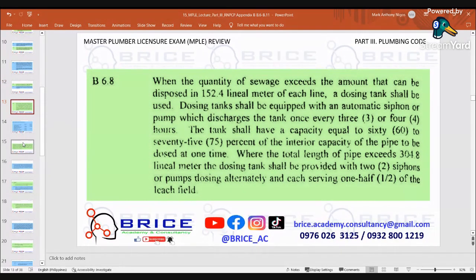When the quantity of sewage exceeds the amount that can be disposed of in 152.4 lineal meters of each line, a dosing tank shall be used. Dosing tanks shall be equipped with an automatic siphon or pump which discharges the tank once every 3 or 4 hours. The tanks shall have a capacity of 60 to 75% of the interior capacity of the pipe to be dosed at one time. Where the total length of pipe exceeds 304.8 lineal meters, the dosing tank shall be provided with 2 siphons or pumps, dosing alternately, each serving 1/2 of the leach field.